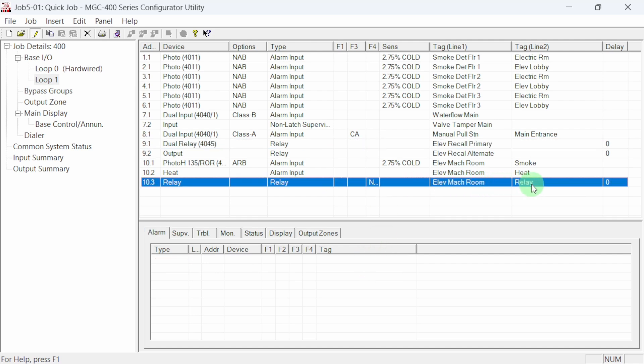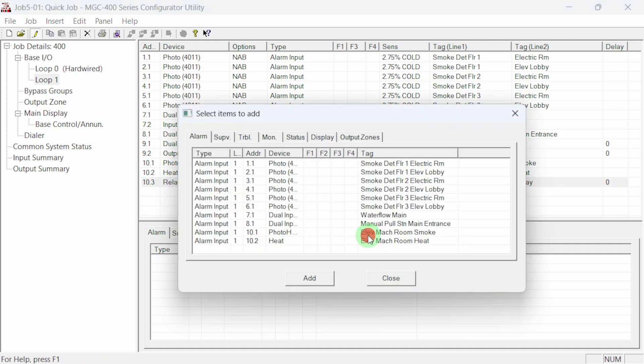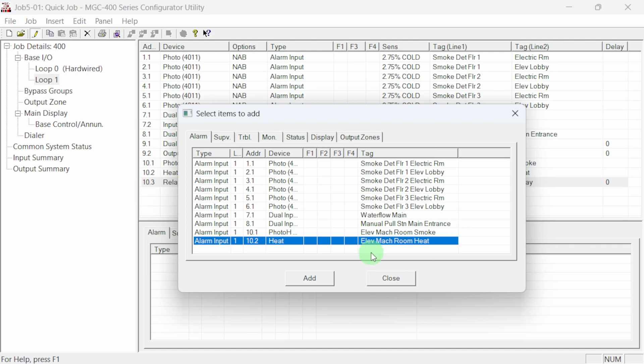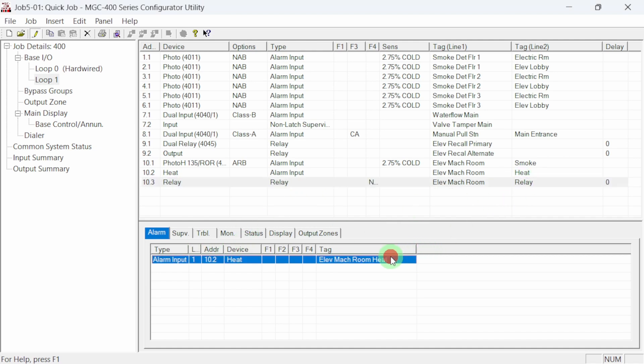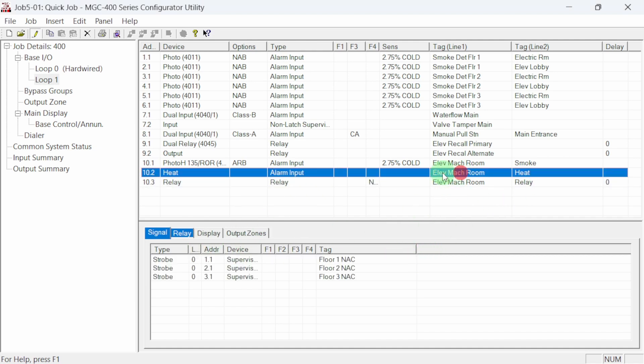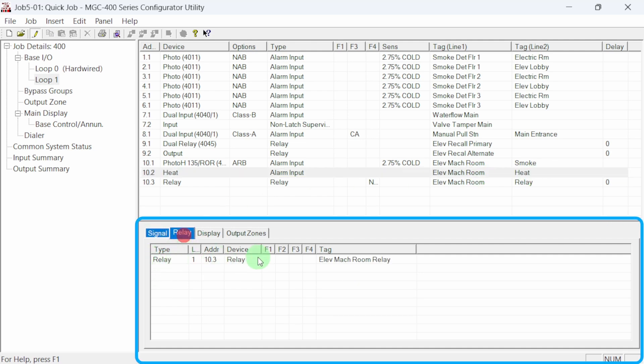The last device that needs to be correlated is the relay base in the elevator machine room smoke detector. In our example, we only want the heat sensor in the photo heat to activate the relay base. Let's right-click on the relay base and add correlations. Choose the elevator machine room heat detector and click add. The relay base is now correlated to the elevator machine room heat detector. If we look at the heat detector, we can see it has the previously correlated NACs and the correlated relay now shows under the relay tab.